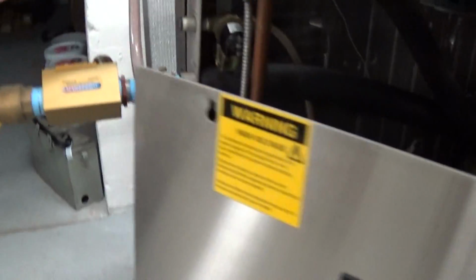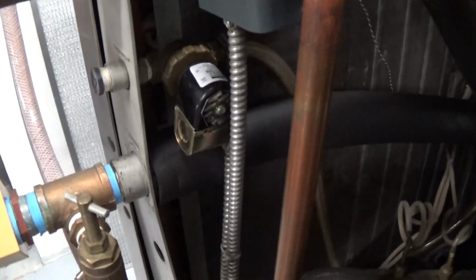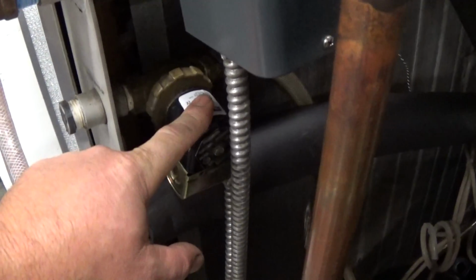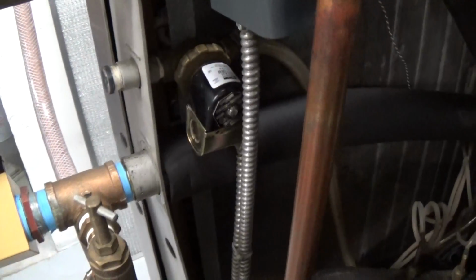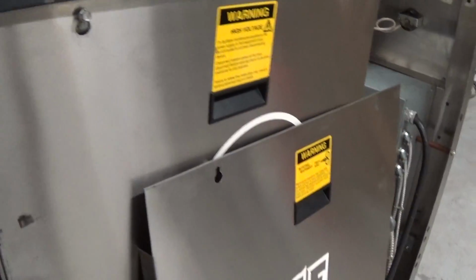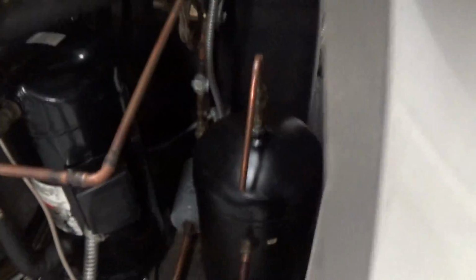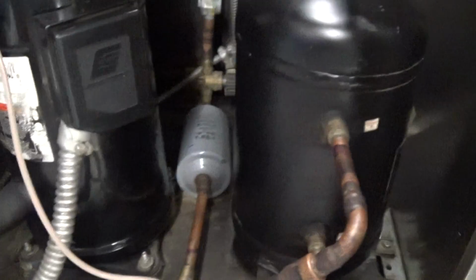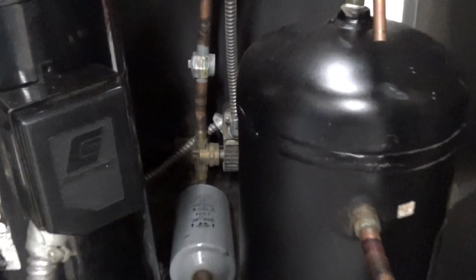Going on the back here. Up top here, kind of nice. You probably don't need to use it for your application, but we do have a make-up water solenoid valve here. We have our 10 horsepower Copeland compressor. Our liquid receiver, dryer. This unit is equipped with hot gas bypass, minimum load control, which is nice. Right above that is your refrigerant sight glass, and also positive line shut off.